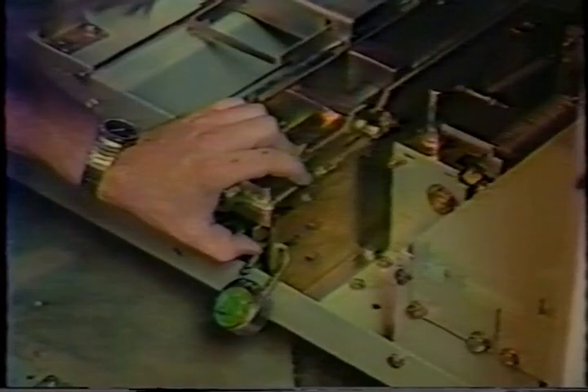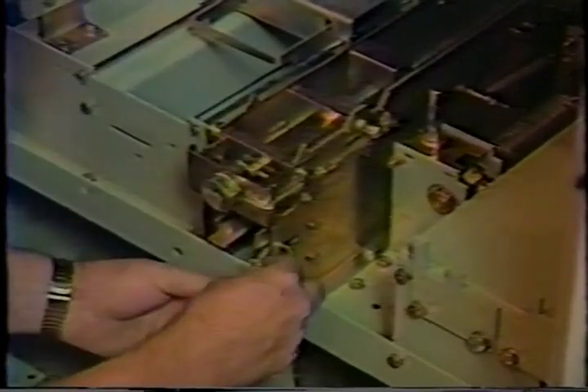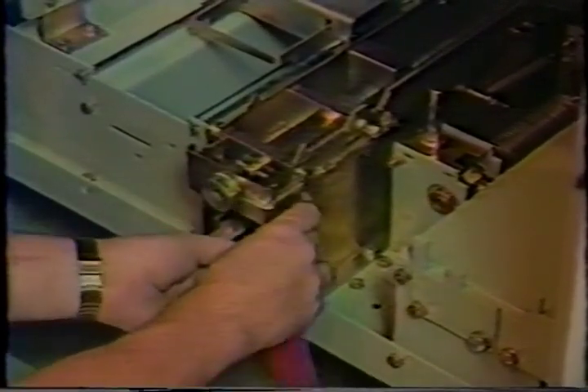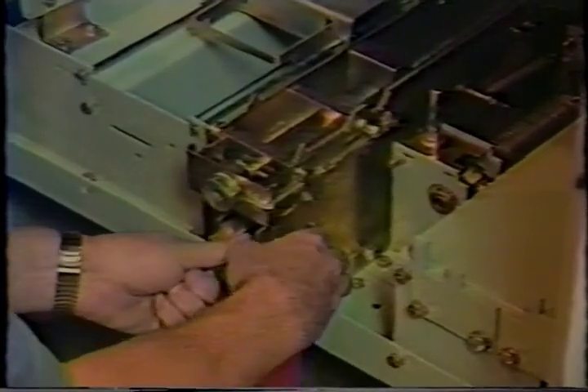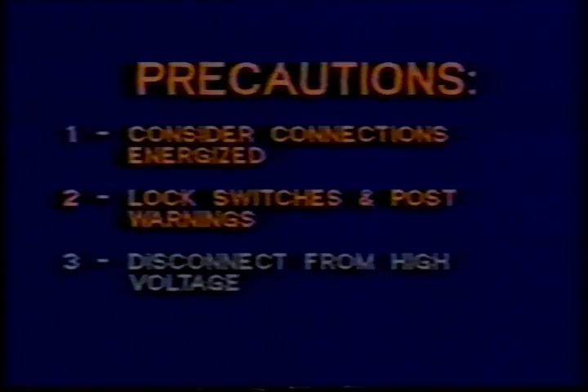Switches or breakers which have been opened to de-energize a circuit to permit work on equipment should be locked or blocked open, and a suitable visible warning device placed on them. Do not work on parts normally carrying current at high voltage until these parts have been disconnected and grounded to the ground bus. Provision should be made by maintenance workers for connecting adequate flexible ground leads to every part of the switching equipment.